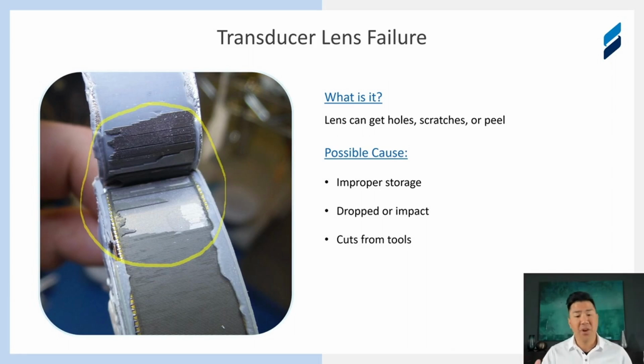So take care of the lens. It's the most important part. It protects the patient from electrical shock as well. It is an insulator between all of the electronics in the probe, and it keeps it away from the patient. It's a very common issue. If you catch it early, the repairability is way high. But if you let it sit for a while, corrosion sets in, and the damage just becomes much more severe as time passes on.